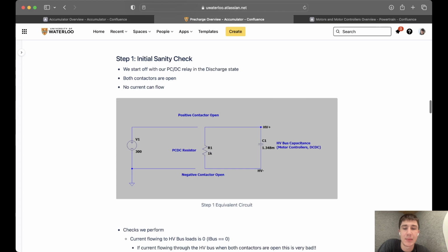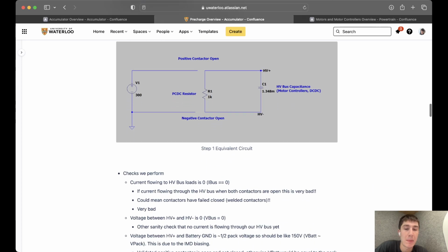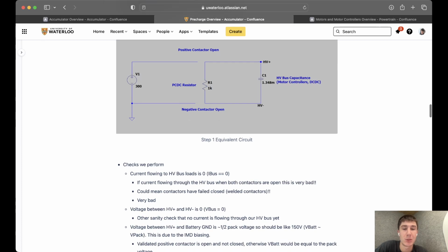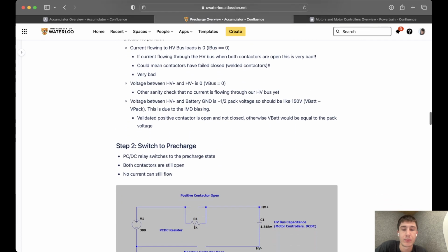So step 1 of our precharge system is we have our high voltage battery, 300 volts, and our positive contactor is open, our negative contactor is open, and our PC-DC resistor is in discharge mode. So you can see we have 1 kilo ohm and it's completely across our high voltage load, our 1.348 millifarad capacitor. So in this situation, nothing's happening. Our capacitor is discharged as there's a resistor in parallel with it and no current is flowing. We perform a bunch of checks here, which I won't go over, but we just make sure contactors aren't welded.